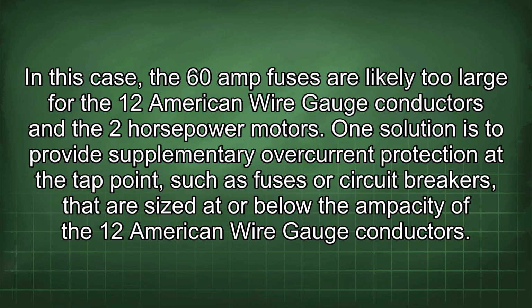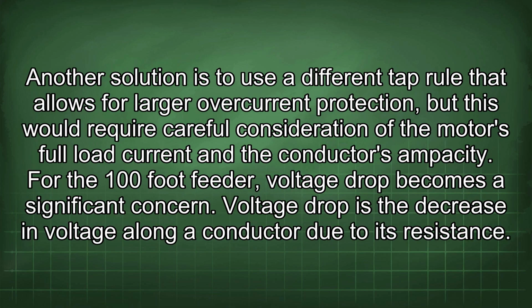In this case, the 60-amp fuses are likely too large for the 12 American wire gauge conductors and the 2 horsepower motors. One solution is to provide supplementary overcurrent protection at the tap point, such as fuses or circuit breakers, that are sized at or below the ampacity of the 12 American wire gauge conductors. Another solution is to use a different tap rule that allows for larger overcurrent protection, but this would require careful consideration of the motor's full load current and the conductor's ampacity.